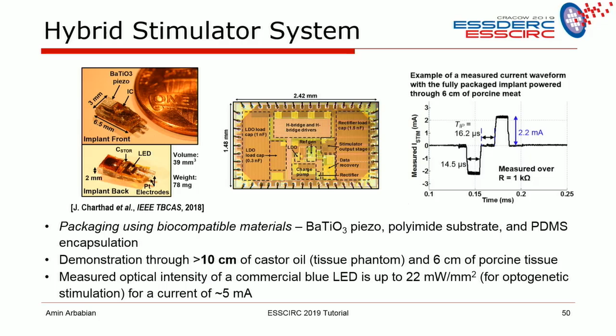You can imagine this is a soft implant, so we use polyimide substrates. We use PDMS and Parylene C interfaces for making sure water doesn't get in. Everything is a soft implant, and you have two platinum electrodes sticking out and the LED sitting on top. We tested this through about 10 centimeters of castor oil and 6 centimeters of porcine tissue, and we can stimulate to about 5 milliamps of current with a barium titanate package, barium titanate piezo.